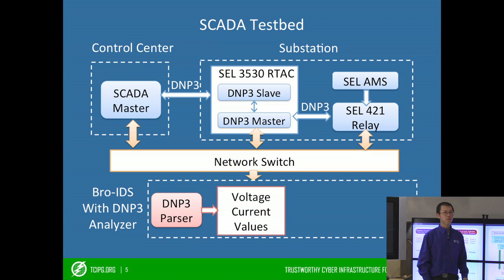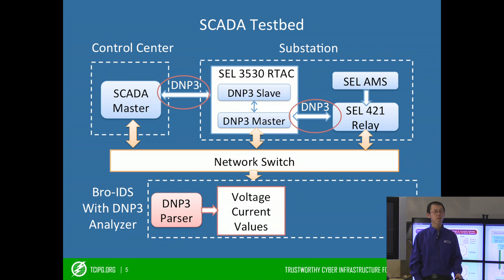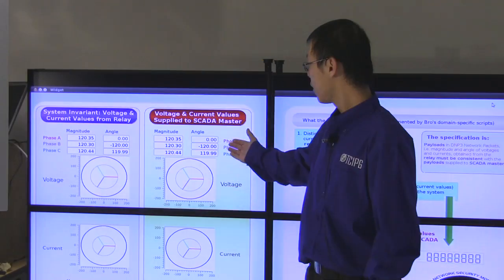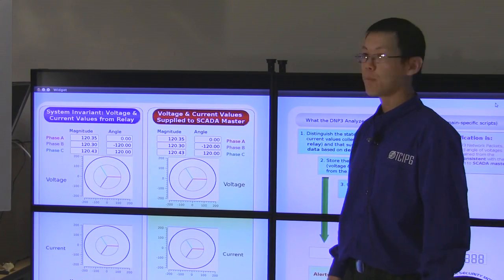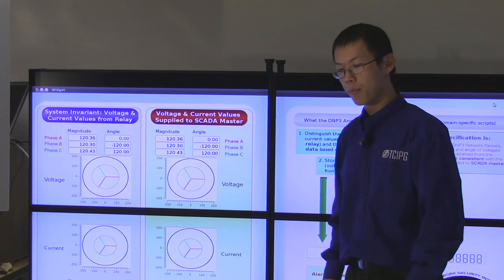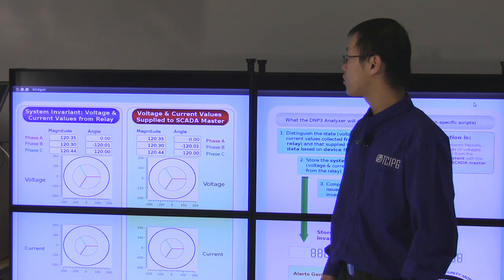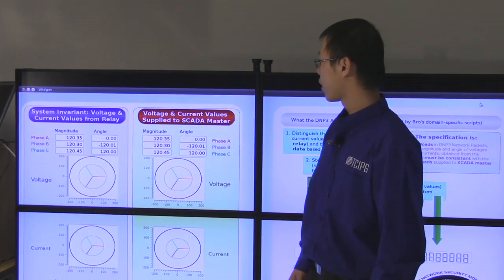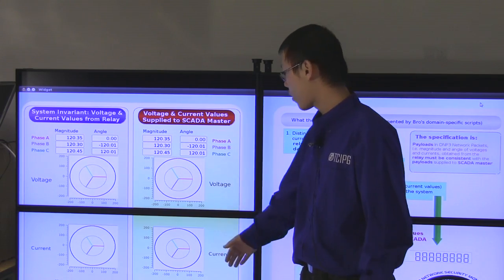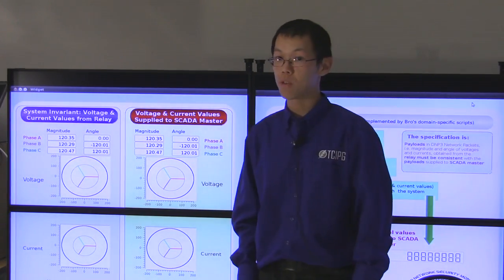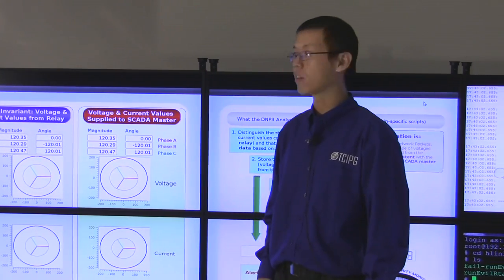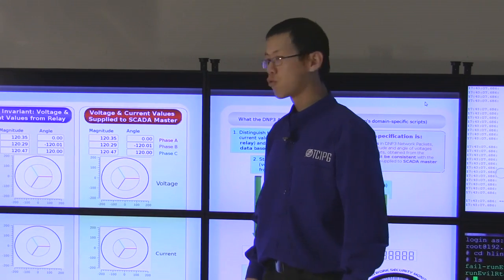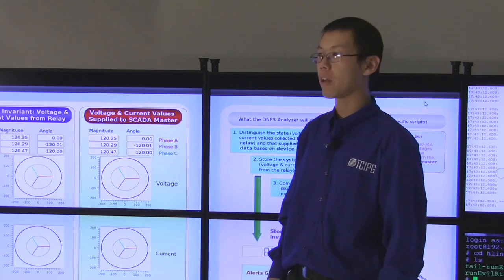The DNP3 parser, a component of the DNP3 analyzer, extracts the voltage and current values from the DNP3 packets on both communications, independent of the security policy we want to use, as shown on this screen. On the left side are the voltage and current values collected from the relay, and on the right side are the voltage and current values provided by the SCADA master. We use the left side values as the system invariant. Voltage is on the upper side and current on the lower side; both contain three phases, and the magnitude and angle of each phase are displayed in those text boxes. We draw vectors to represent each phase according to its magnitude and angle.